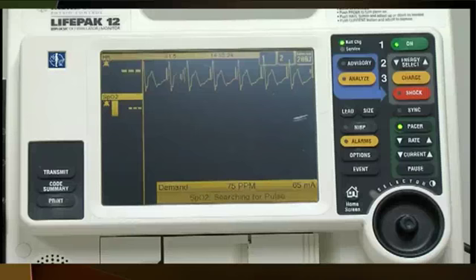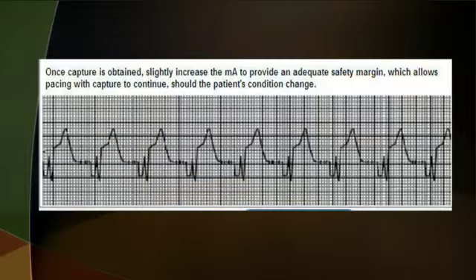So what you would do is hit the pacer button, so you'll see that little green light that's in the button come on. Turn your rate to where you want it to be, and then where it says current, that is milliamps, so it's automatically on 0. You have to increase that in order to start pacing the patient. Once capture is obtained, you should slightly increase your MA to provide an adequate safety margin. This allows pacing with capture to continue should the patient's condition change.